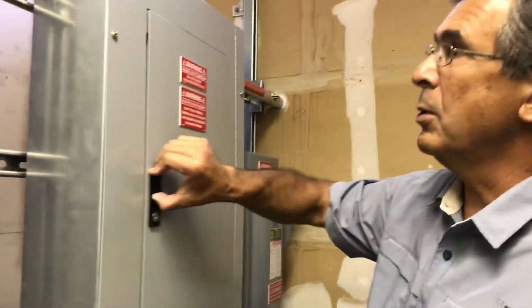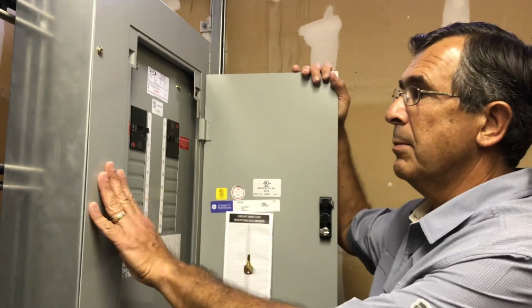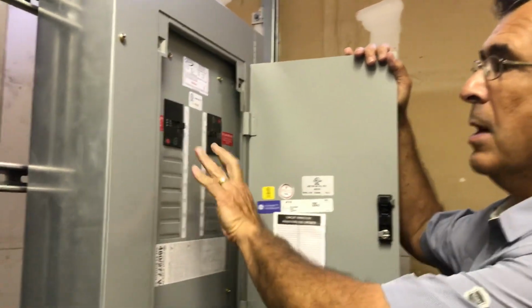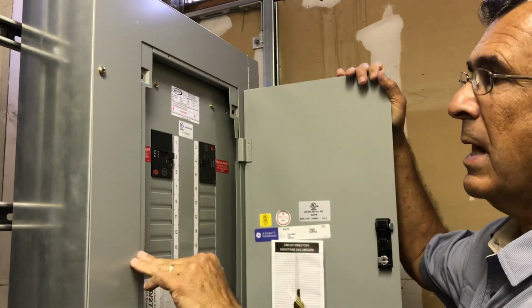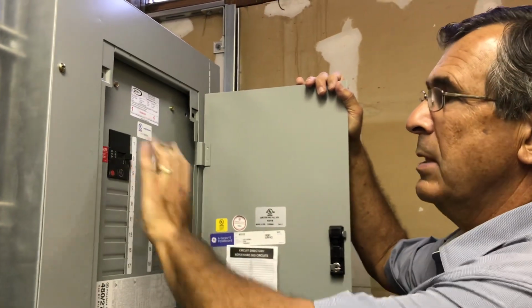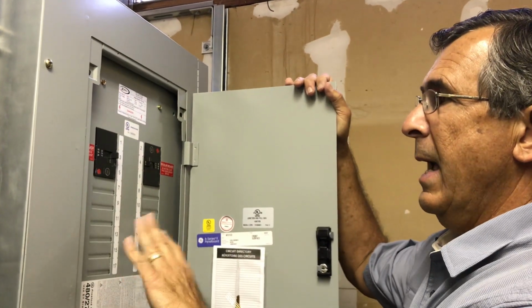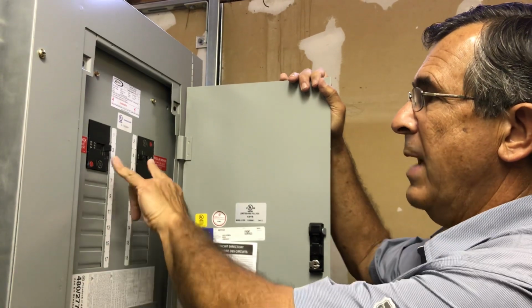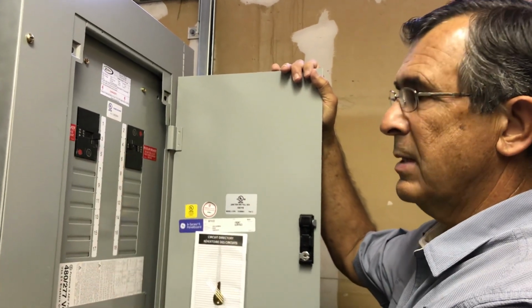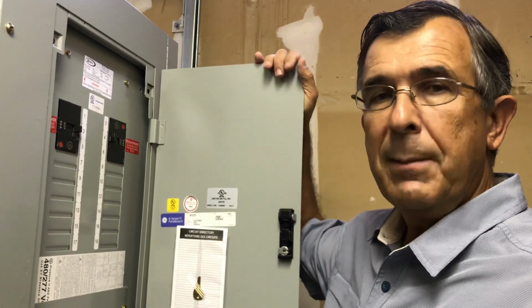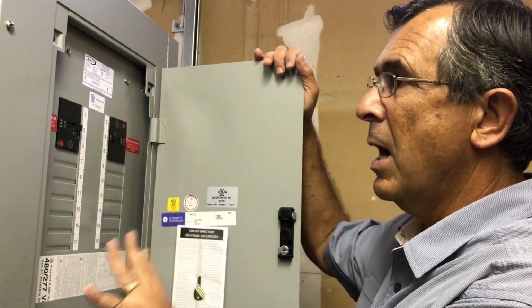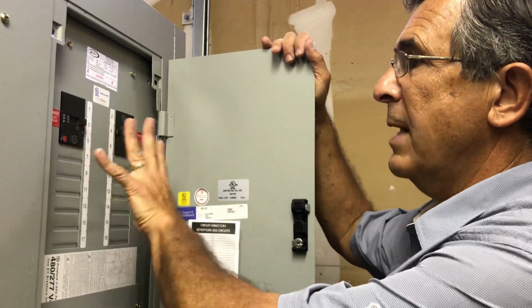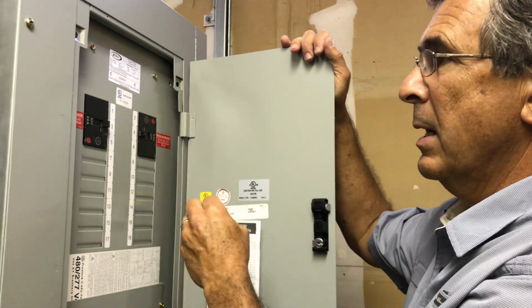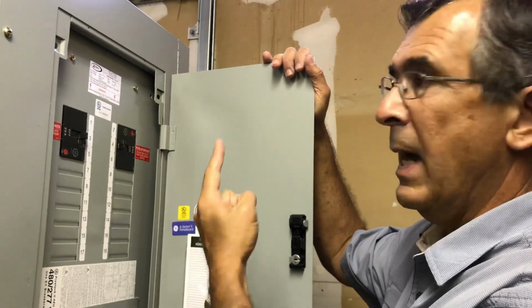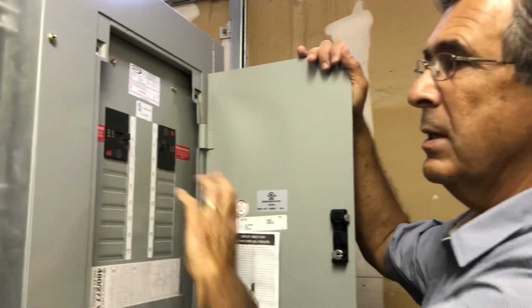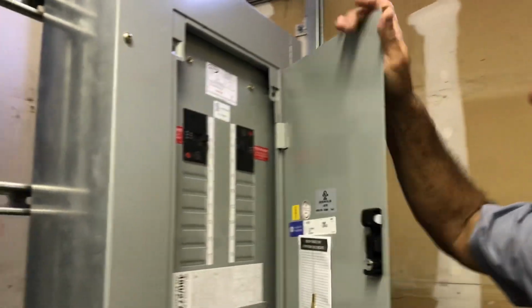The first thing we need to do, if we have multiple inverters, is combine them. In this situation, we have two 33.3 kilowatt inverters out in the carport, so we've combined those in what we call a load center here. And we've had load centers similar to this, where we've had 10 of these circuits on both sides, combining many inverters into a common circuit. So we bring all that voltage into one area and essentially create one out of many. So these two 50 amp circuits now leave as a 100 amp circuit.